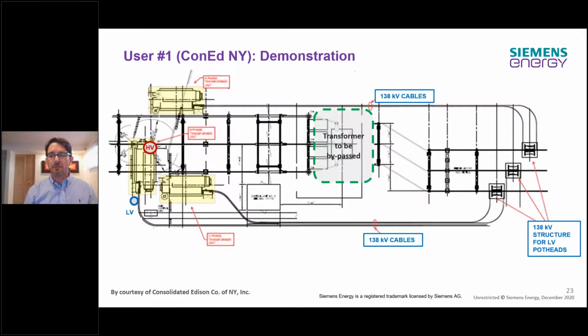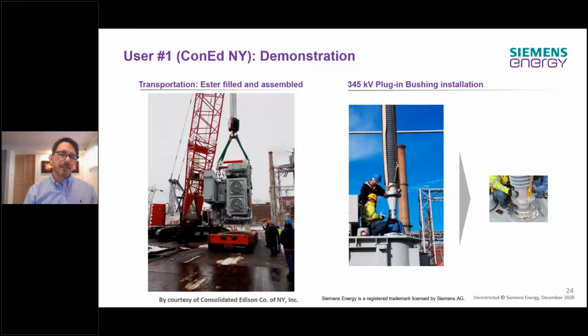And then the cables go to a structure that was also developed for low voltage potheads to connect the 138 kV bus bar. And here are some pictures as well. In the first picture, you see the transformer being lifted with a crane, and that transformer was actually transported from the warehouse to the substation ester filled. It was liquid filled. So we saved time by avoiding having to fill the transformer on the pad.